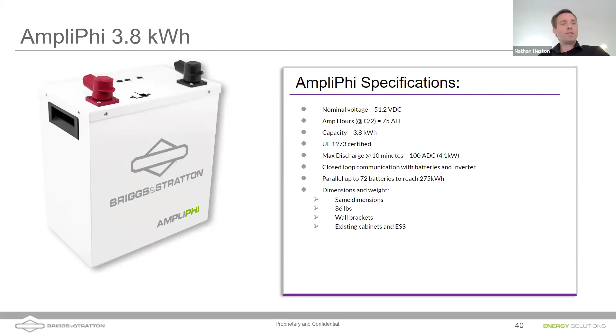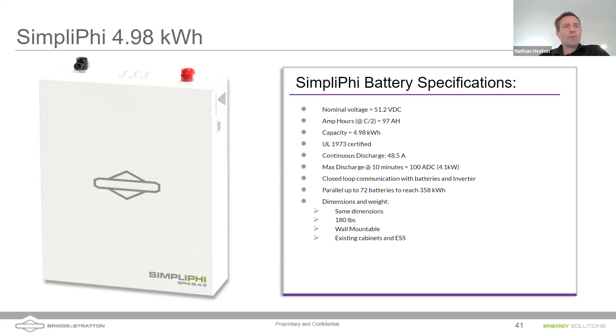This is, again, the same battery pack inside there. We're using the same high-end cells in this battery, but you've got a more sophisticated communicating BMS. This is an outdoor rated 4.98 kilowatt hour battery, essentially a 5 kilowatt hour battery. It's rated at C/2, but it's also rated for outdoors. It's a waterproof battery. It can surge at 100 amps. If needed, a single battery can output 4 kilowatts for up to 10 minutes.